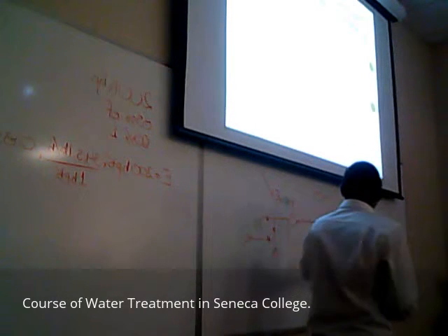Now we want to know the blowdown. For the blowdown, we need to know the cycle of concentration. The cycle of concentration is going to tell us how many times the water has to go into the system before we have to discharge this water.